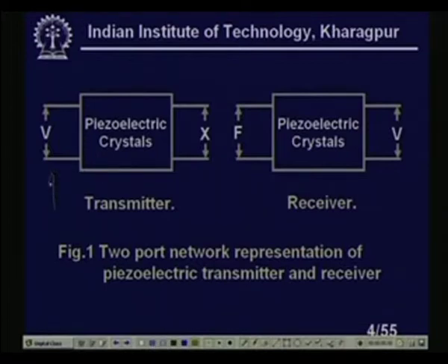Applying a voltage signal here, I am getting a force here, and it is reversible. If I apply a force, I will get a voltage. That is the typical principle of the ultrasonic sensors, or the piezoelectric crystals, I should say. We are using those properties of the piezoelectric crystals to generate the ultrasonic signals.